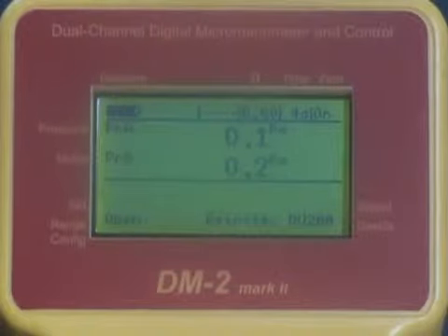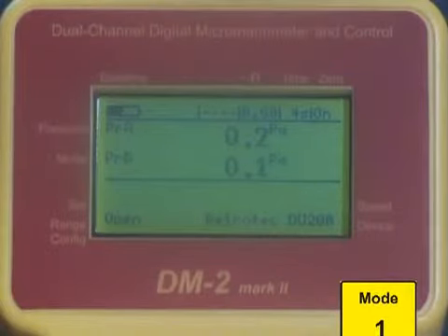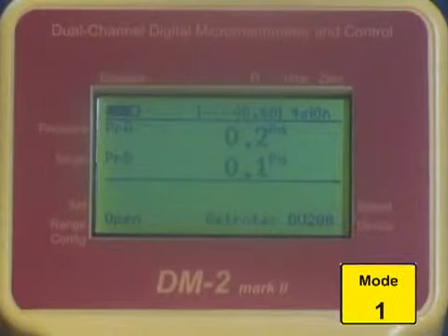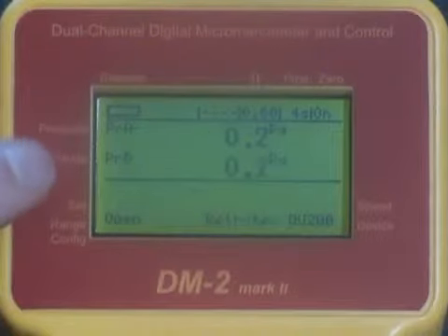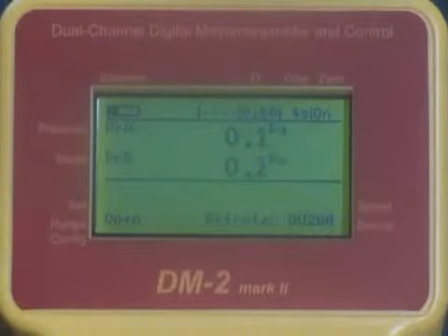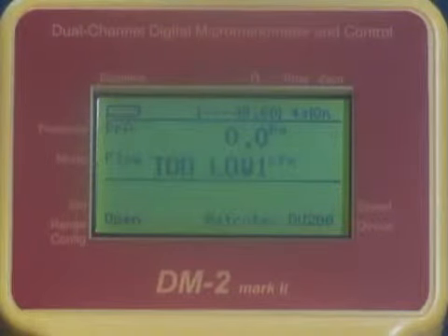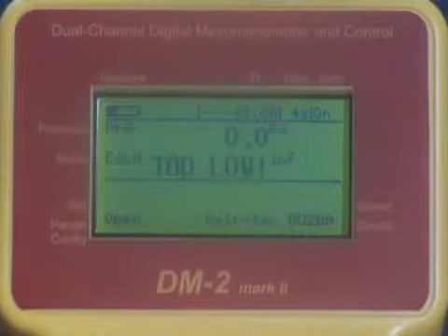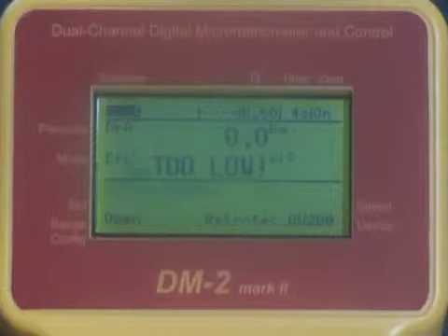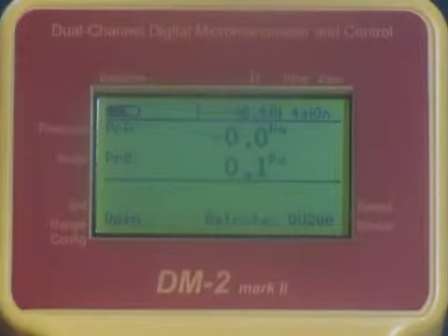So today we're going to talk about the mode key, which is the top left-hand key on your keyboard, and I'm just going to press the mode key on this unit and see what happens. So the mode key controls mode right here, which is the second channel of this gauge. On this particular gauge, the first time we press it we get CFM, then we get square inches of EQLA, then we get EFLA in square feet, and we get air changes per hour, and then we go back to pressure B. Obviously some of these you want, some of these you don't want, and you may want some additional input. So let's take a look and see how we can change that.